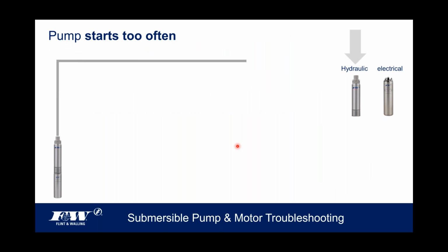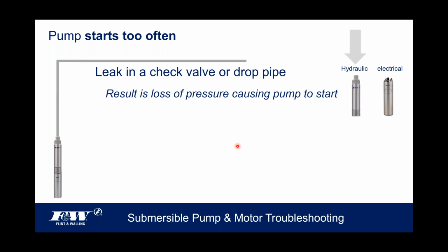Let's go to this one here. It's not a situation anymore where the pump doesn't shut off. It just starts too often. I mean, every time I turn around, the daggone thing's running. Okay. Again, if you have any leaks, that leak could be in the check valve down here at the discharge of the submersible, or if you have any leak in that pipe, anything that will cause a loss of pressure, right? Pressure eking out is going to start that pump up.